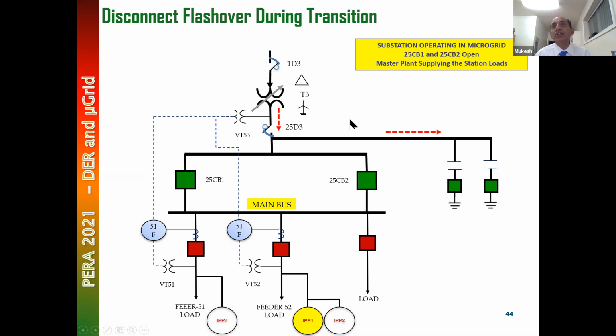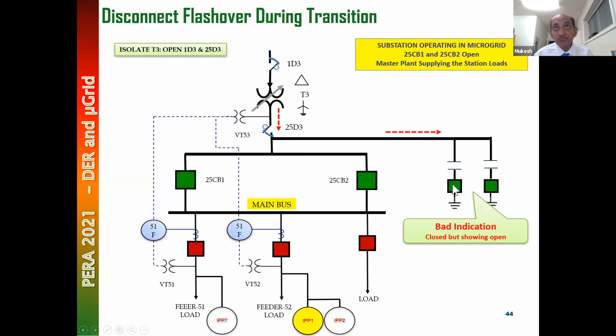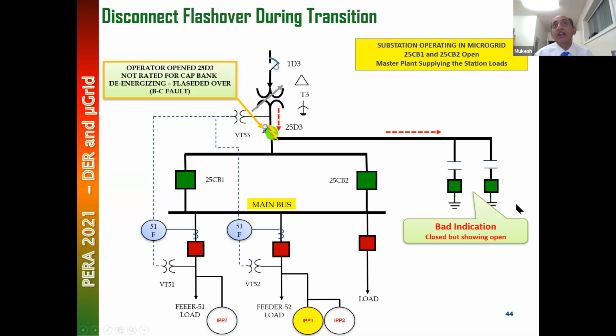So in the process of a switching sequence, the operator wanted to check this transformer before closing this thing. He wanted to do some check. So the operator opened this disconnect to isolate this transformer. He thought this disconnect can only open when there is no current. If there's a current here, this disconnect cannot open. So this was a bad indication. Because there was a current flowing, this disconnect was not meant to interrupt the current. And therefore, when it tried to interrupt a current, it flashed over and caused a real fault.